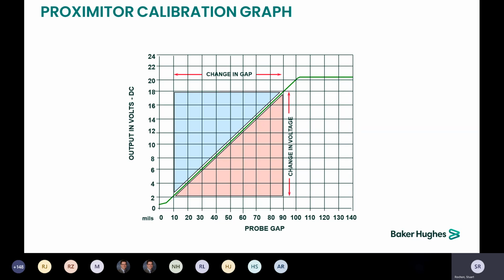To check them, you take the probe out of the machine, you put it into a spindle micrometer cradle, and you basically set your spindle micrometer to 0. You butt your probe up against the spindle micrometer target and lock it down.